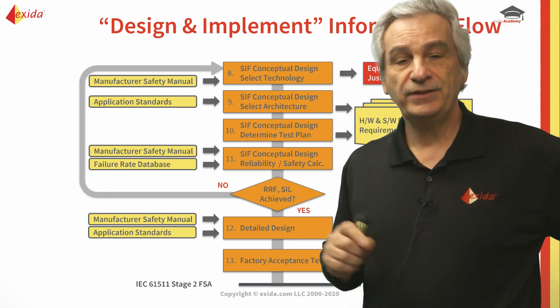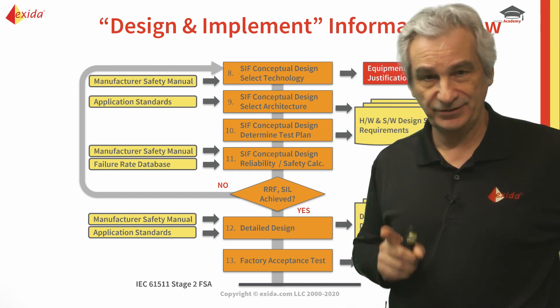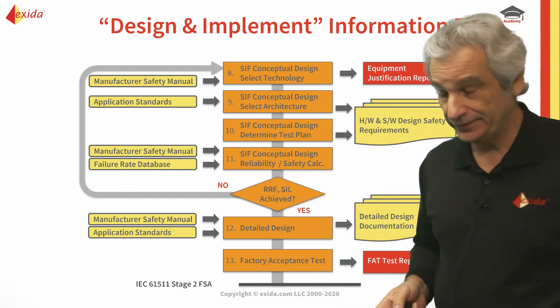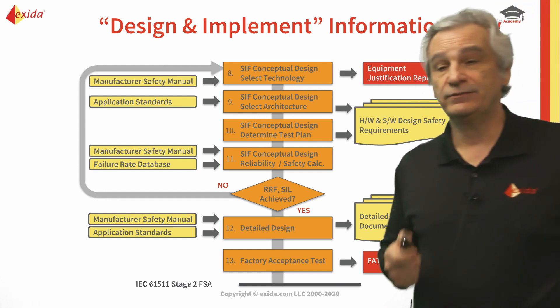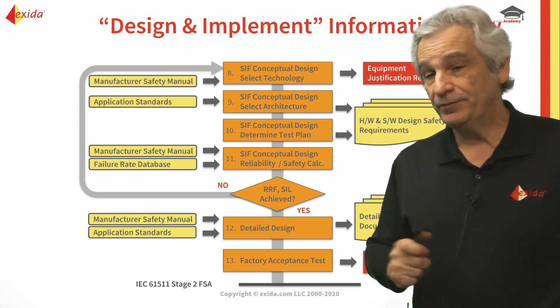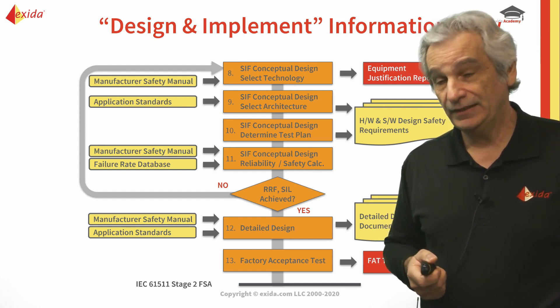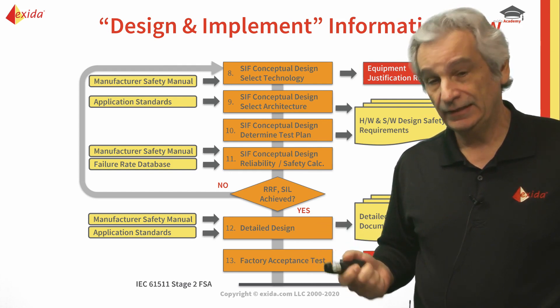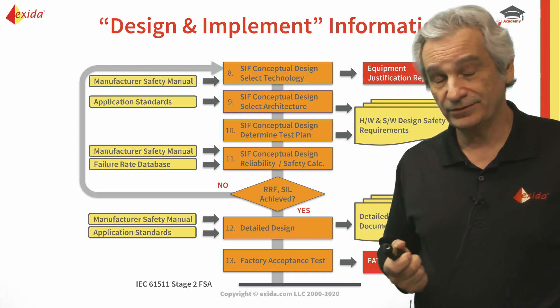Once we've determined how we're going to test it, we do our SIL verification, which is iterative until we meet the requirement. In the 102 course you'll find there are three things you must meet for SIL verification compliance. A lot of people think it's just the PFD average for low demand, but it's not — it's either PFD average or PFH for high demand or continuous, plus the architectural constraints, i.e., does it need to be fault tolerant.